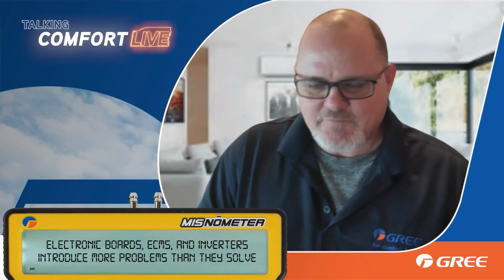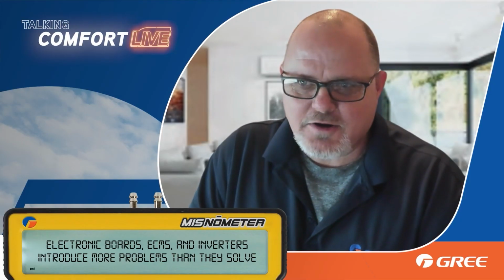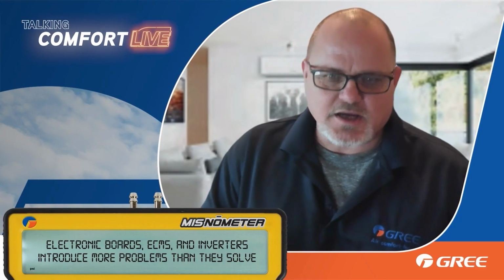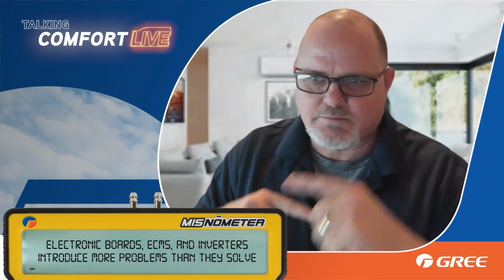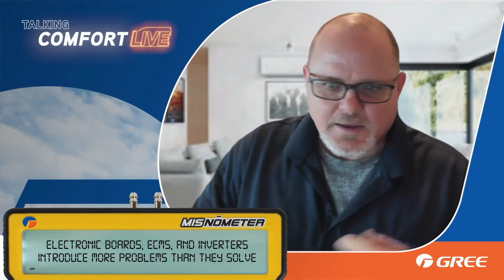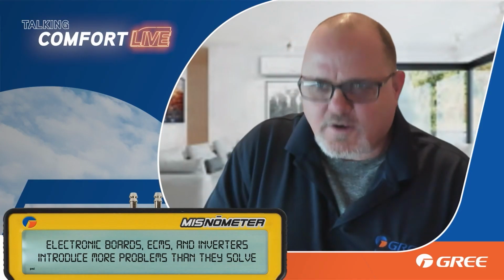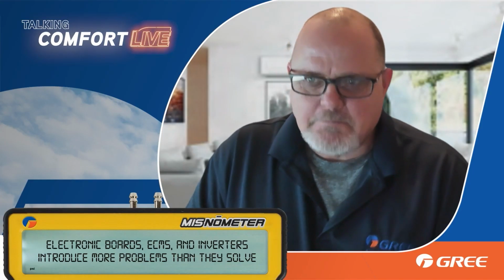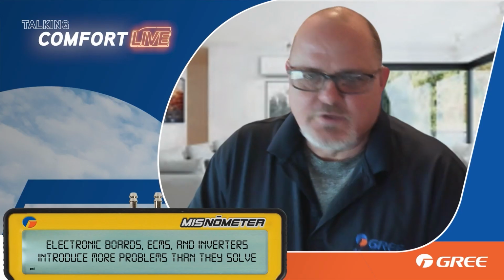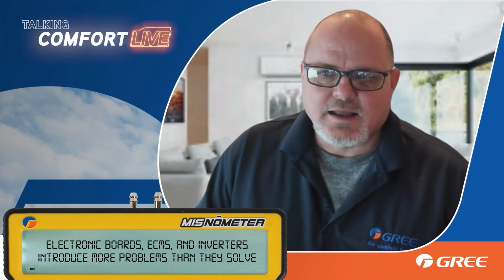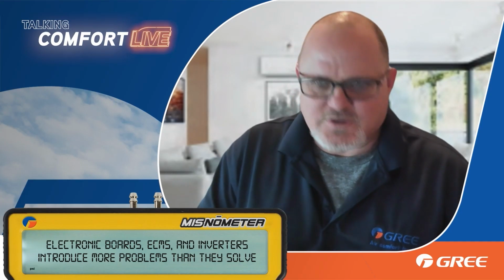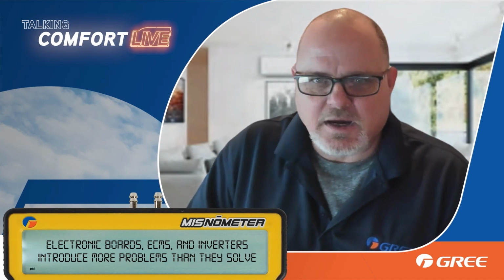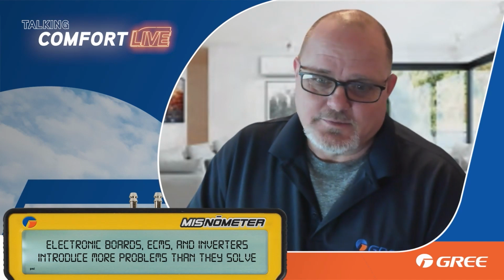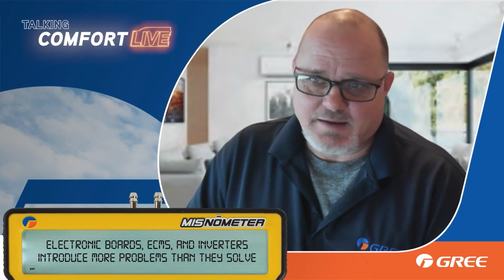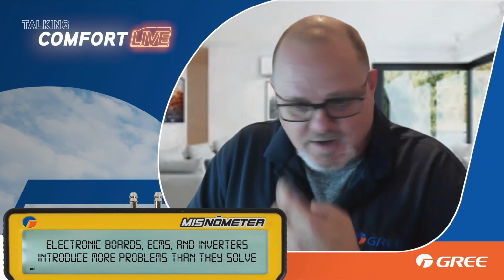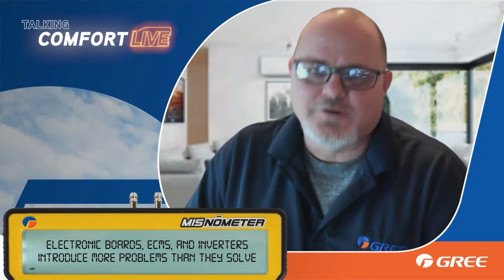But if that had that VFD on there, you'd never hear that, because the VFD is just like an inverter driver. So now it's going to start that blower up nice and slow. You're never going to get that high torque on that belt and get that belt squeal. You'll never have that complaint again. Now, it doesn't mean the belt can't go bad and wear and stuff like that. Still need belt changes, but you're not going to get that squeal. Not at startup. And I know people listening to this broadcast have all heard that.